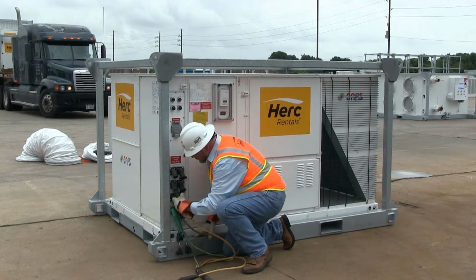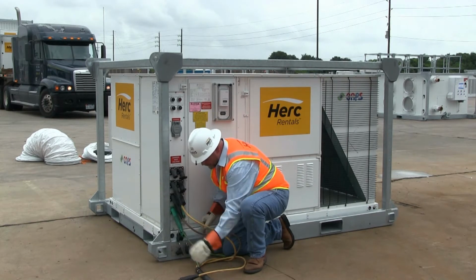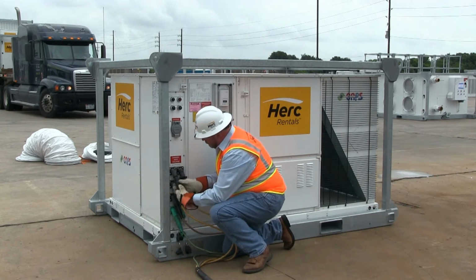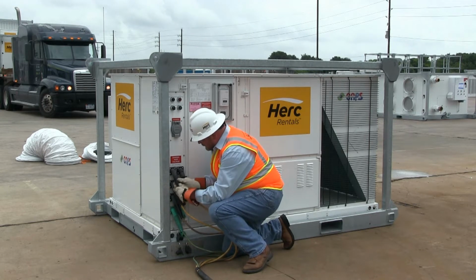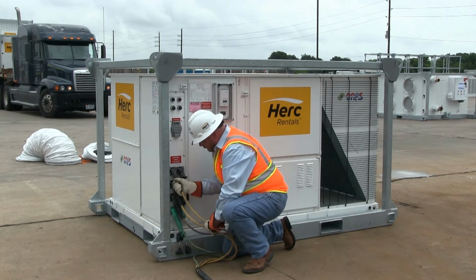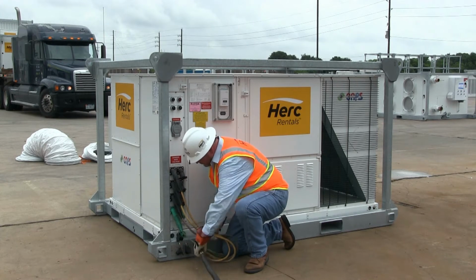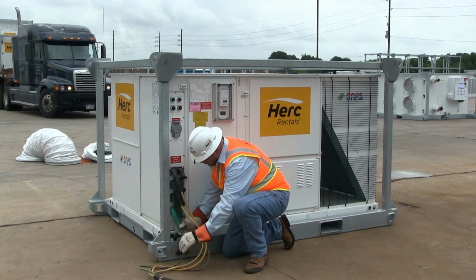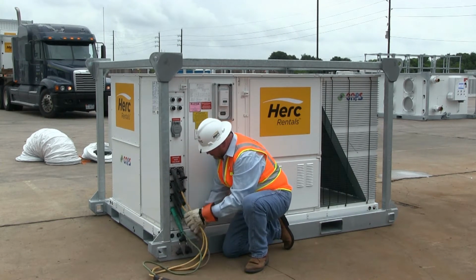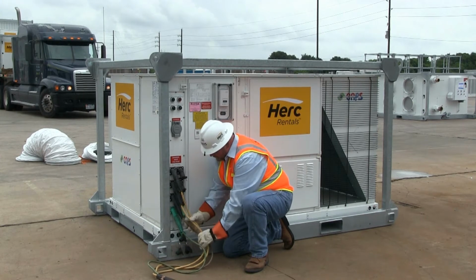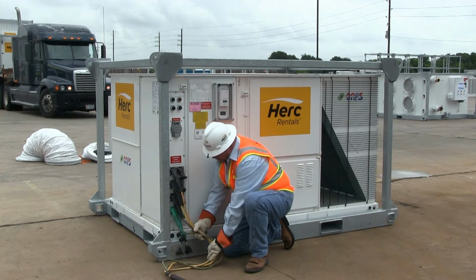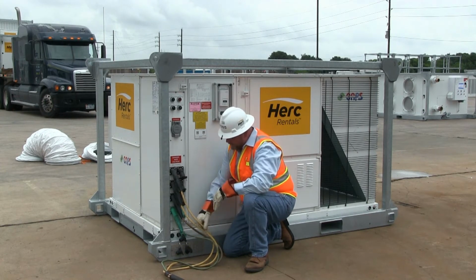Then we're going to check rotation to see if we have the correct phase before operating the machine. The machine does have a phase monitor that will determine if the phase is correct. You want to always hook up the ground wire first, followed by the L1, 2, and 3. Now we have our power source currently locked and tagged out. We're going to energize it to check phase.